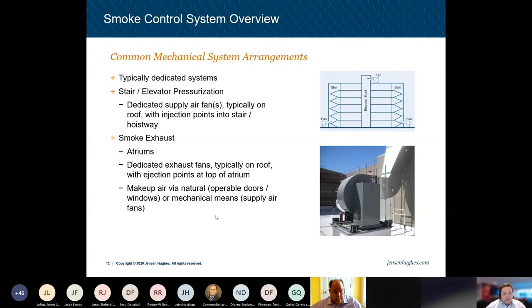Some common mechanical system arrangements for newer smoke control systems. Typically, these are dedicated. They are at least required to be for stair and elevator pressurization. You'll typically see a dedicated supply fan, usually on the roof, unless it's a super tall high rise, with injection points into the stair and hoistway. With smoke exhaust and atriums, you typically have dedicated exhaust fans that are also on the roof with ejection points at the top of the atrium. And then for makeup air, you'll see that via natural openings, so that could be operable doors or windows, or mechanical means with supply air fans.